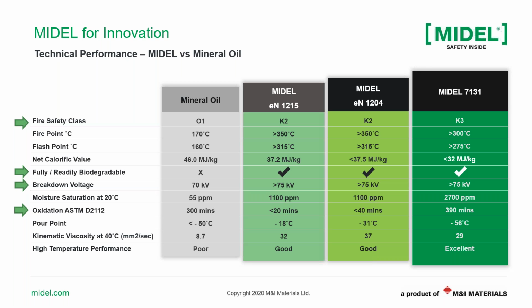Another item here I thought to share, and I will talk about it later more, is the breakdown voltage. Of course, these fluids are dielectric fluids. Their main purpose is to create this insulation within the transformer. Under AC conditions for this test, esters and mineral oil are comparable in behavior, and so we expect the AC breakdown voltage to be higher than 70 kV in normal application and in a transformer.